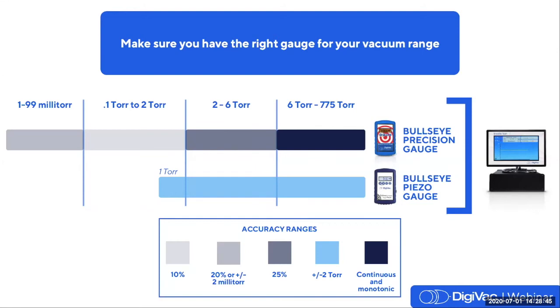The bullseye precision gauge, as with most thermocouple type instruments, is really at its most accurate from a couple of millitorr up into about 6 torr. That's merely a function of the technology of the sensor that is standard in terms of thermocouple type instruments. That is the range with accuracy. We consider from approximately 1 to 99 millitorr to be 10% of reading. From 0.1 torr up to 2 torr is 20% of reading, or 2 millitorr.